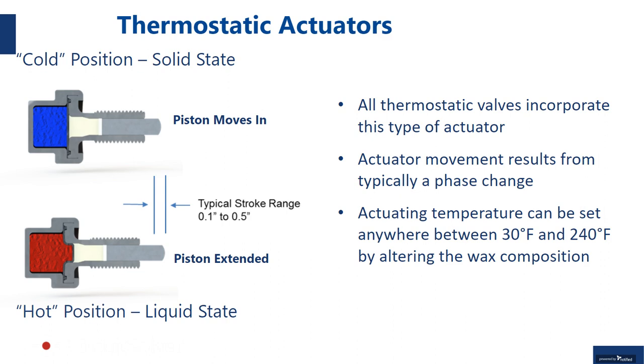So this type of technology, again, has been around for well over 100 years. Freeze protection valves, which are somewhere in the area of 30 degrees Fahrenheit, and high temperature shutoff valves, which can be in excess of 240 degrees Fahrenheit, basically all use this same type of actuator with different wax formulations. So again, very reliable, very simple. There's no shelf life associated with the paraffin wax. It doesn't change its characteristics over time.